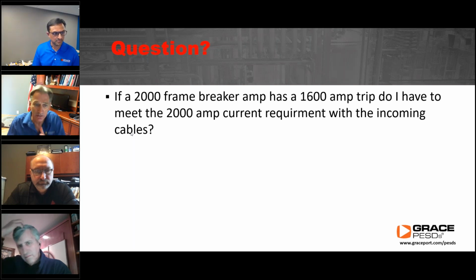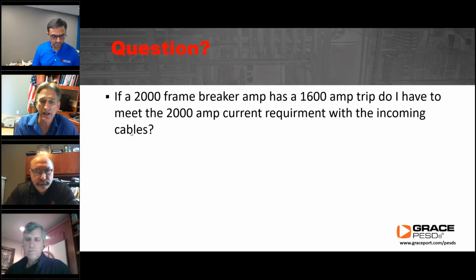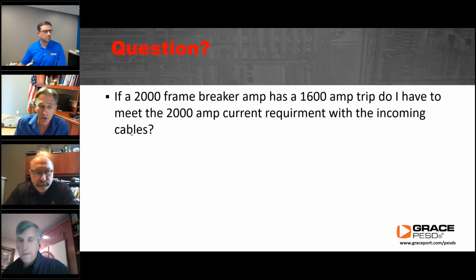C is titled Restricted Access Adjustable Trip Circuit Breakers. And this section says a circuit breaker that has restricted access to the adjusting means shall be permitted to have an ampere rating that is equal to the adjusted current setting, long time pickup setting. And it goes on to say restricted access shall be defined as located behind one of the following. And there's three that it gives us.